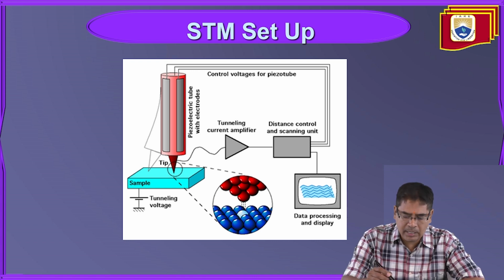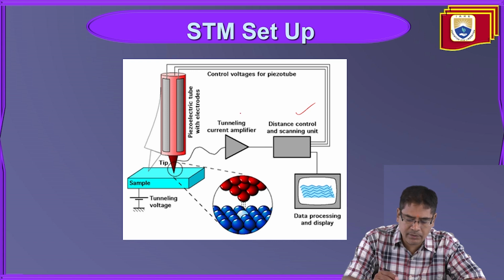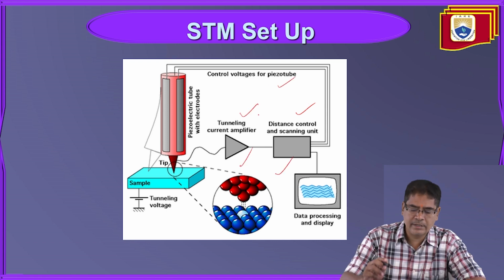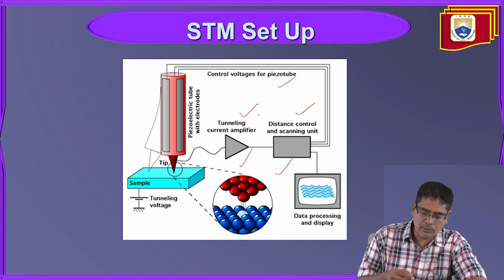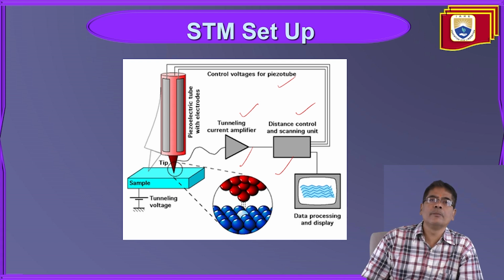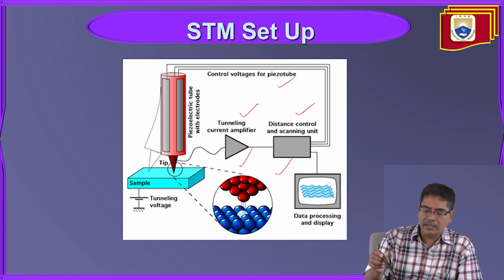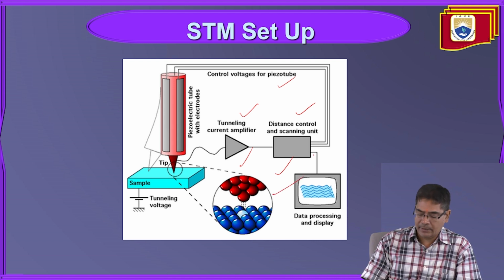We have distance control and scanning unit. We have tunneling current amplifier, control voltage for piezoelectric tube. This is what the tunneling voltages we have. Okay, tunneling voltage and the sample specimen where it needs to be kept, and the tip interacts with the sample, and we can see the imaging here, right? So this is the imaging effect we can see here.